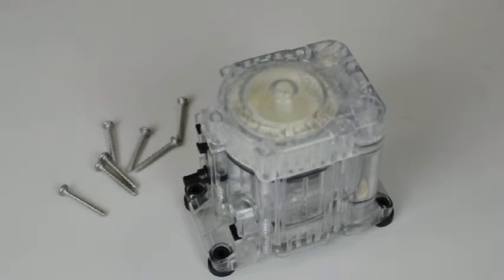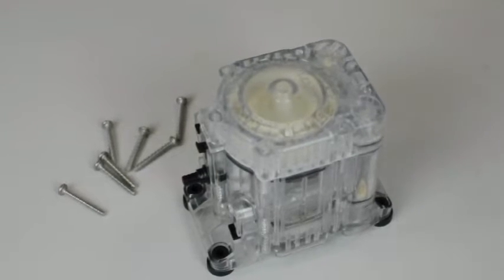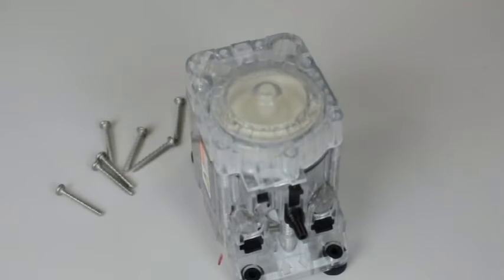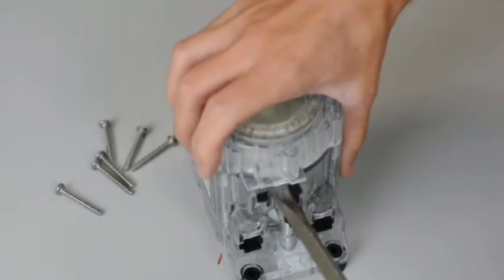Now that we've removed all seven screws, I'm going to take a flat head screwdriver and very carefully remove the upper body housing. I'm going to make sure that the inner flange is held downward so that we don't damage the diaphragm.